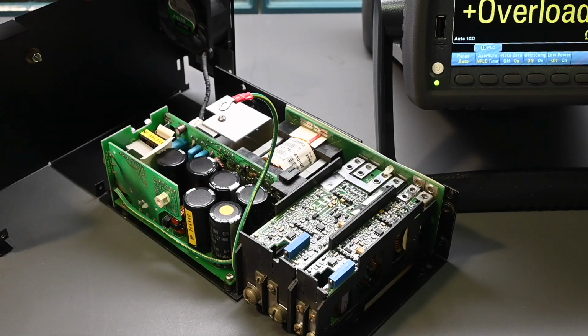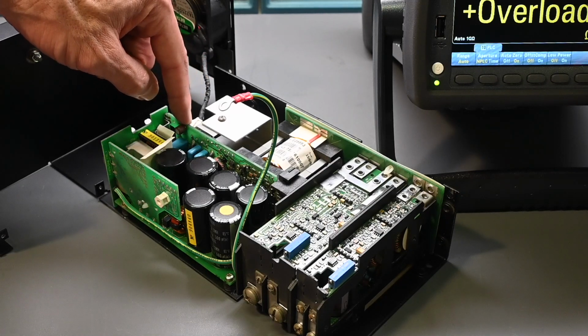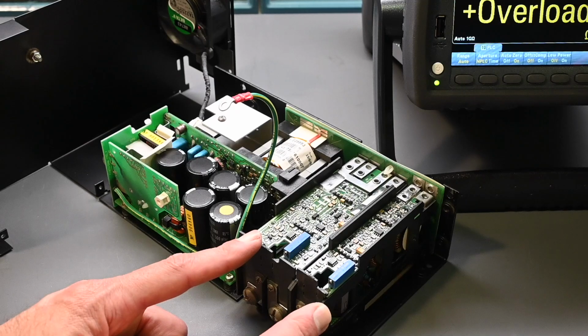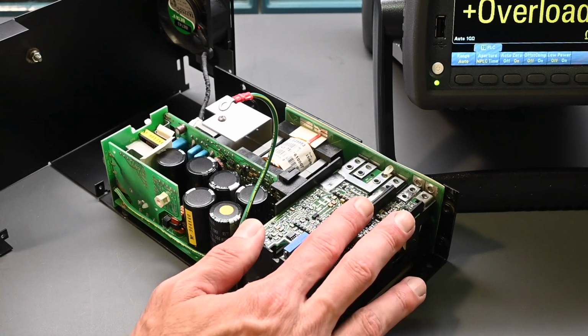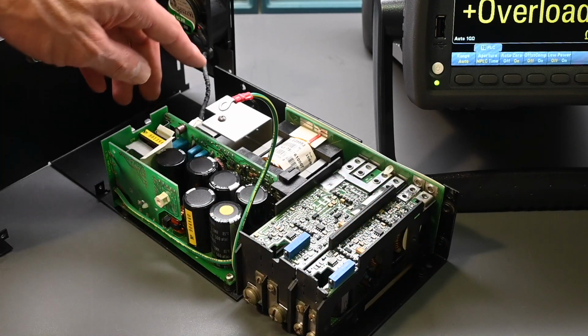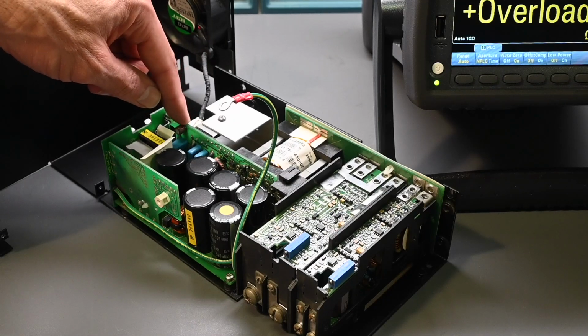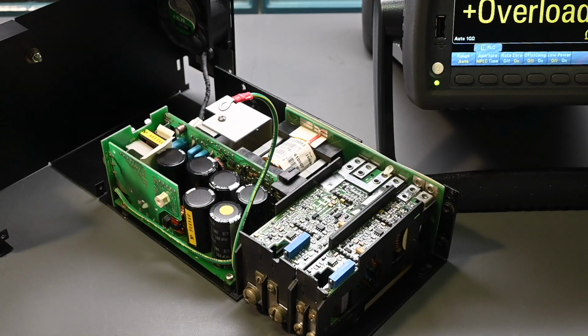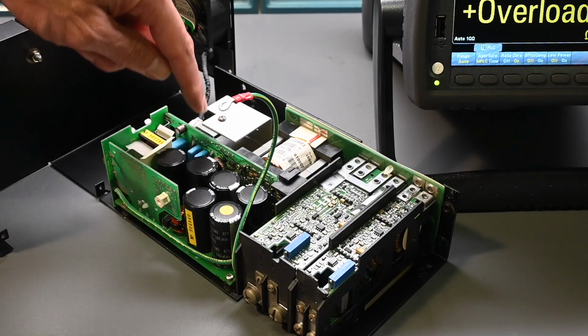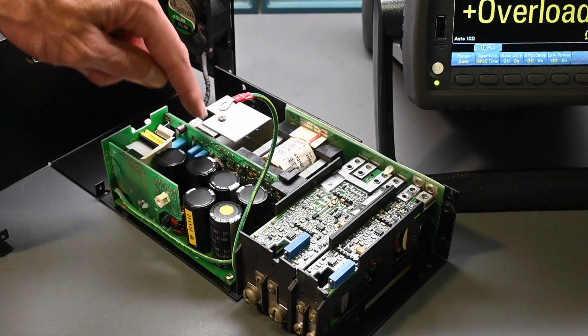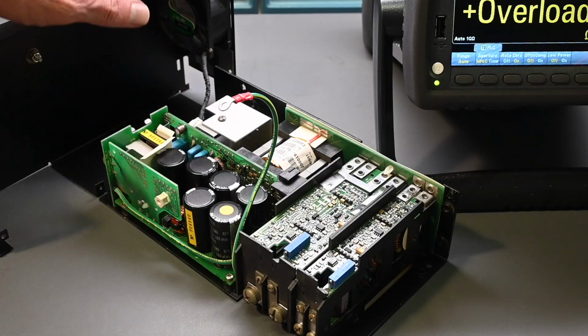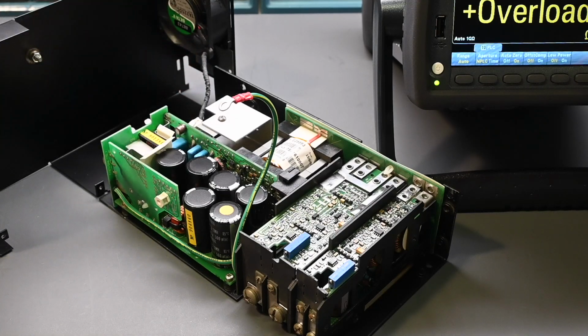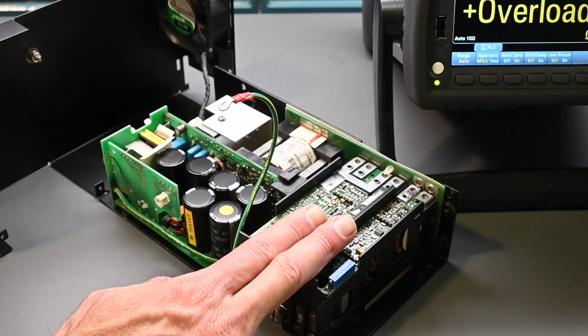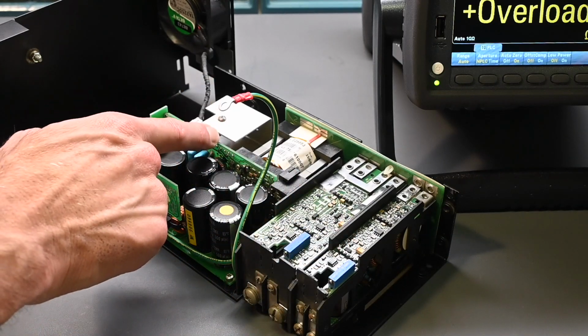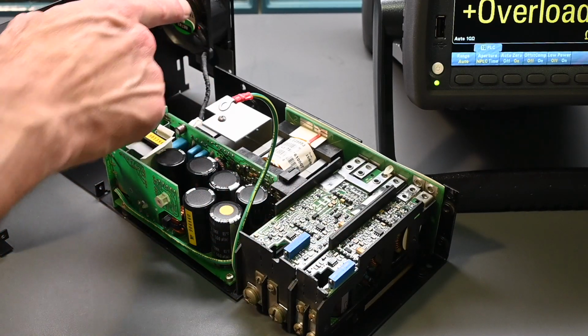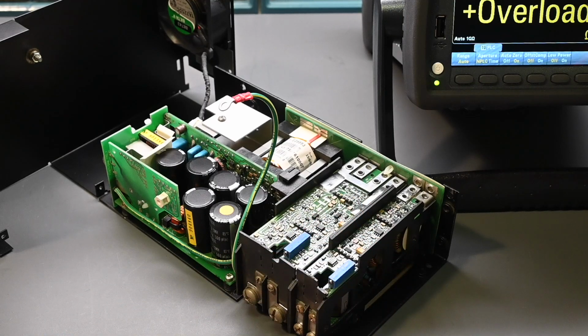This fan plugs into the circuit board here, but the output is taken over here. This output could be configured many different ways depending on the modules, but the fan always gets its voltage off of this board, and the fan doesn't want to run. So I'm wondering if the problem could actually be on this circuit board, because the voltage here isn't even correct, since it can't operate the fan. If the problem was over on the other side, I'd expect this board to have correct voltage and the fan might run, but the output of the power supply would be incorrect.